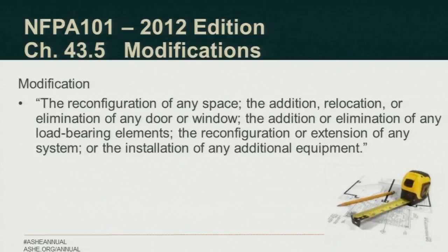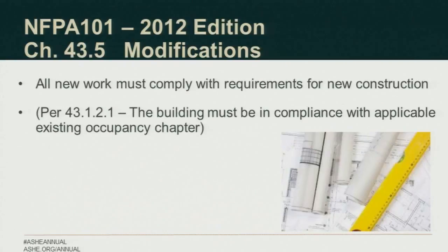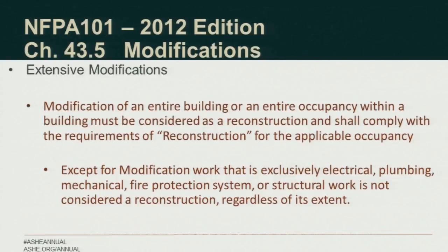Okay, so modification, we read the definition. We don't need to rehash that. All new work must comply with new construction. It's not requiring upgrade of areas, but all the new work must comply with new construction. Again, the building must be compliant with the applicable NFPA occupancy chapter.